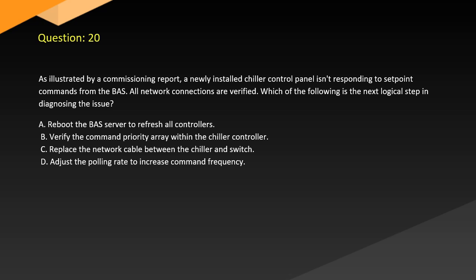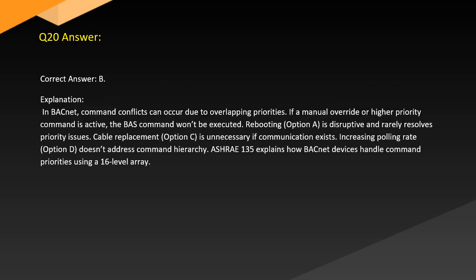Which of the following is the next logical step in diagnosing the issue? A. Reboot the BAS server to refresh all controllers. B. Verify the command priority array within the chiller controller. C. Replace the network cable between the chiller and switch. D. Adjust the polling rate to increase command frequency. Answer. Correct answer: B. Explanation. In BACnet, command conflicts can occur due to overlapping priorities.